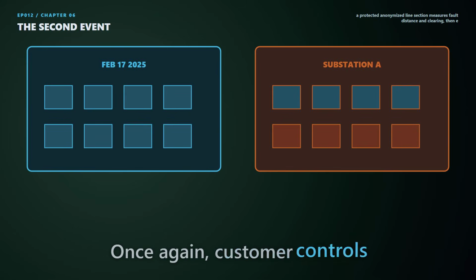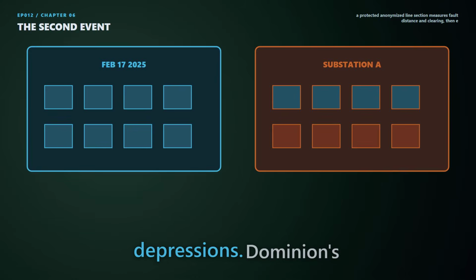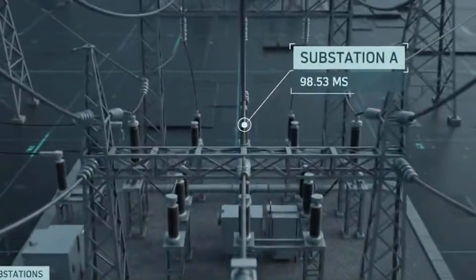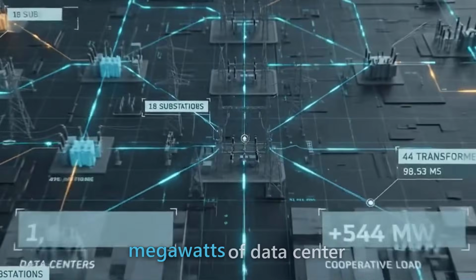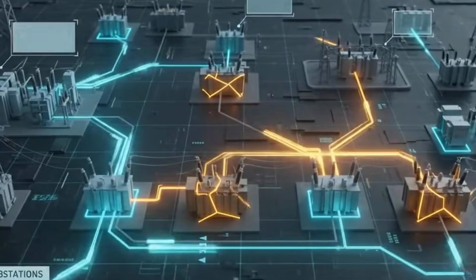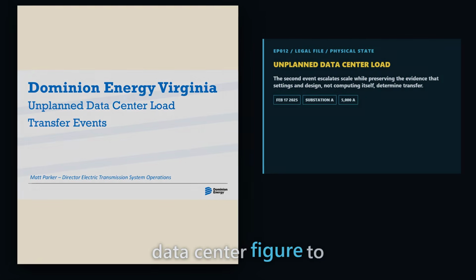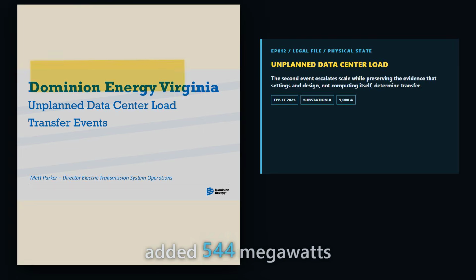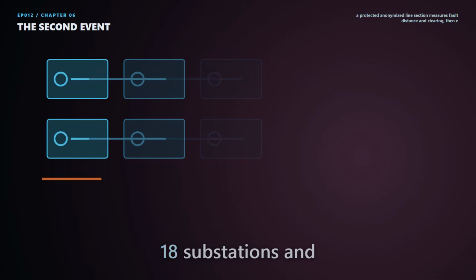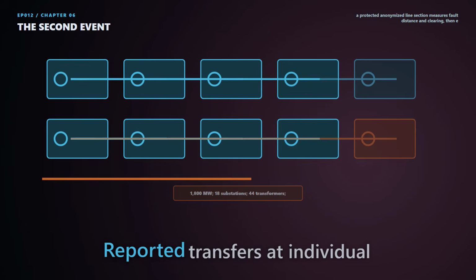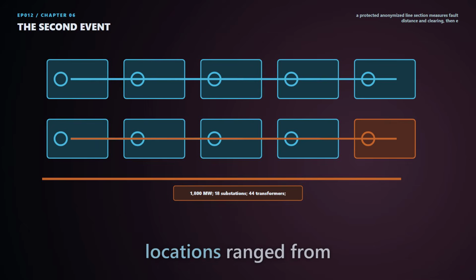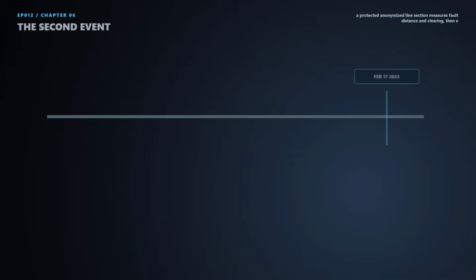Once again, customer controls watched the resulting voltage depressions. Dominion's early investigation described approximately 1,700 megawatts of data center load transferring. Later presentations revised the data center figure to 1,800 megawatts and added 544 megawatts of cooperative load. The data center portion affected 18 substations and 44 transformers. Reported transfers at individual locations range from 4 to 154 megawatts, averaging 75.